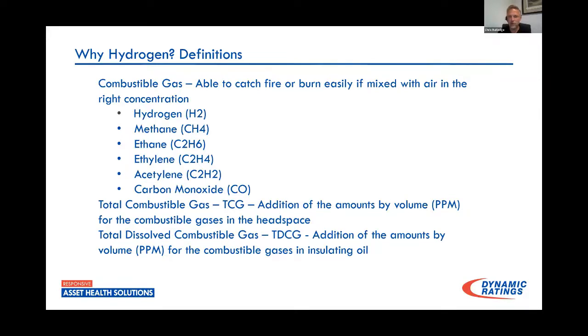So just quickly running through, with hydrogen, I would expect to see some methane development. They both start generating around 150 degrees C. So I would expect to see that. Where we're really looking is also if we have acetylene. So if we have acetylene building up and we have ethylene, and ethylene is about 10% of our acetylene values, we have some active arcing occurring with that transformer. With hydrogen and mostly methane, we know we probably have a PD type thing occurring.